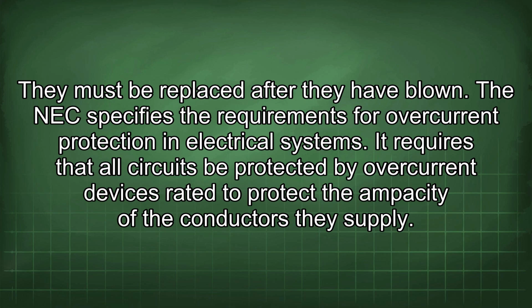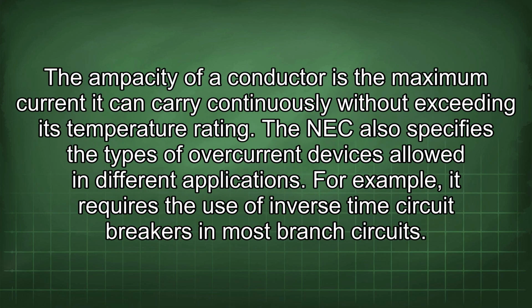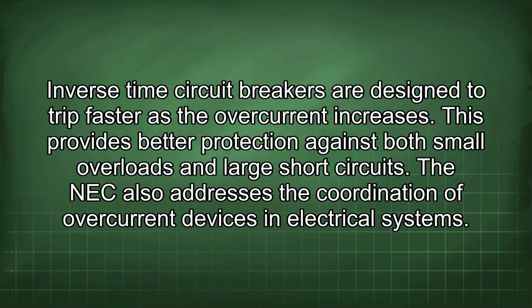The NEC specifies the requirements for overcurrent protection in electrical systems. It requires that all circuits be protected by overcurrent devices rated to protect the ampacity of the conductors they supply. The ampacity of a conductor is the maximum current it can carry continuously without exceeding its temperature rating. The NEC also specifies the types of overcurrent devices allowed in different applications. For example, it requires the use of inverse time circuit breakers in most branch circuits. Inverse time circuit breakers are designed to trip faster as the overcurrent increases. This provides better protection against both small overloads and large short circuits.